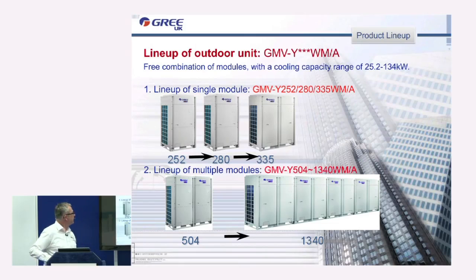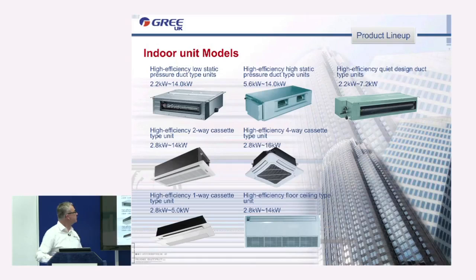So what about the range? Well, basically these units come in modular form, as with most VRF, and it ranges in its entirety from a 25.2 kilowatt module, and then by combining the modules together, we can have up to a maximum of 134 kilowatts in the PV VRF system. The range of indoor units is basically the same as all our VRF indoor units. So we need no special indoor units. We need no special wiring or piping or anything like this, away from what we normally do with our VRF system. So the full range of indoor units is connectable to this system. This is just some of the units available. There are more. So it just shows us that basically we can treat it like it is any other VRF system.